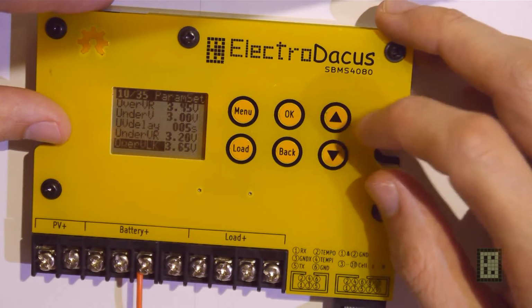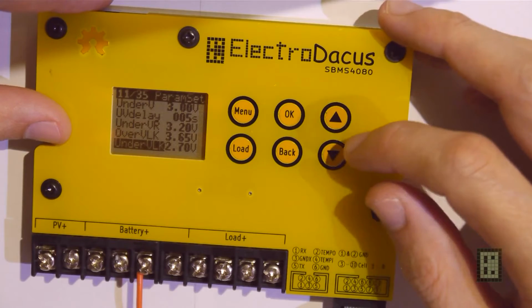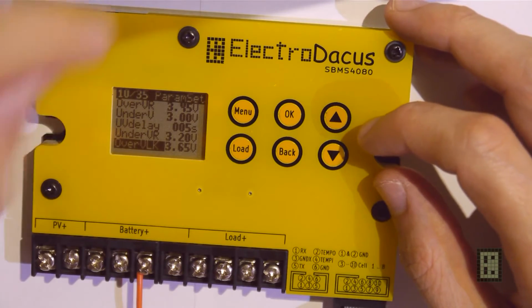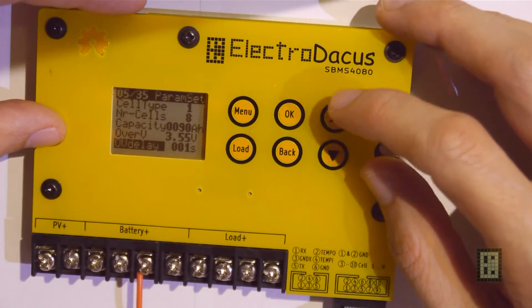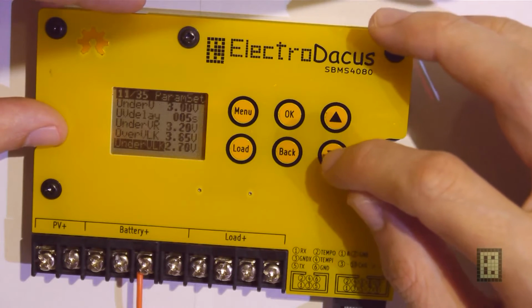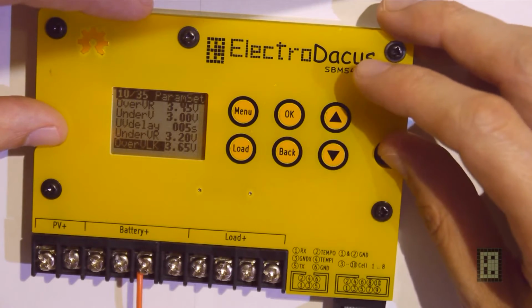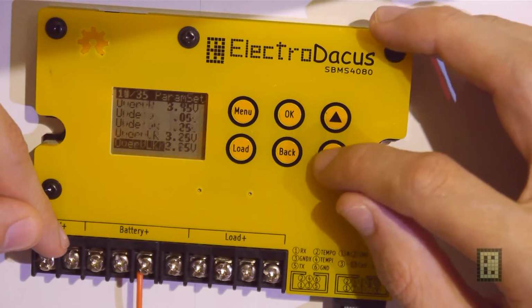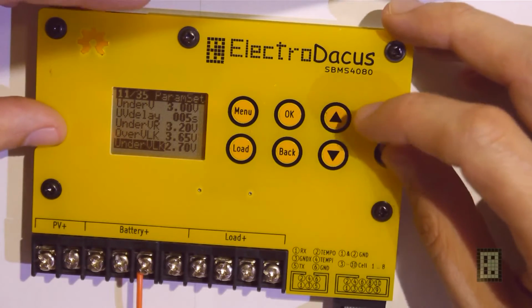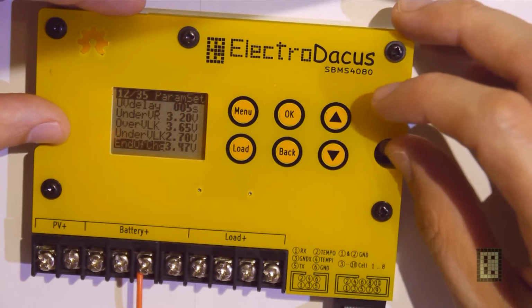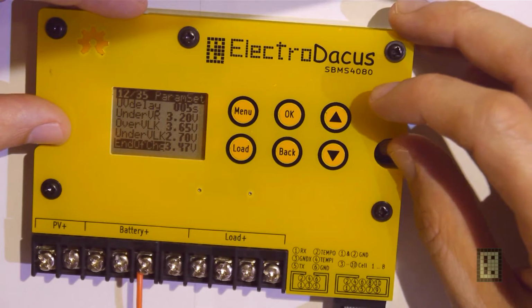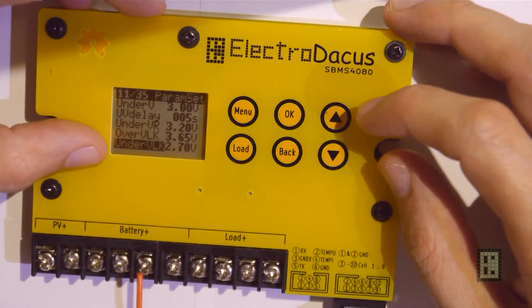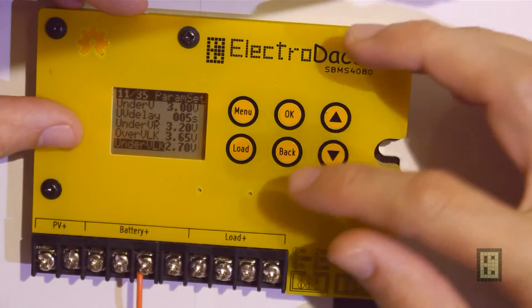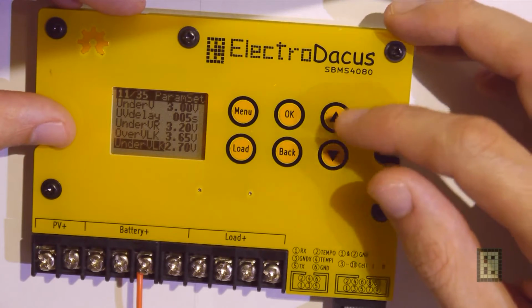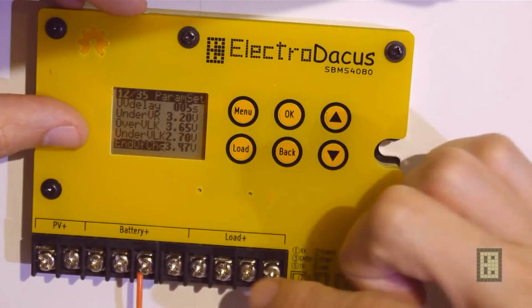Okay, over voltage lockout. This should probably never happen, but just in case you had some wrong parameters in there, like this delay being very high or something like that, then when it gets to this level it will shut down the charging anyway, without waiting for any delay. And this is the under voltage lockout, same thing. If the battery gets to this level, it will immediately cut off the load.